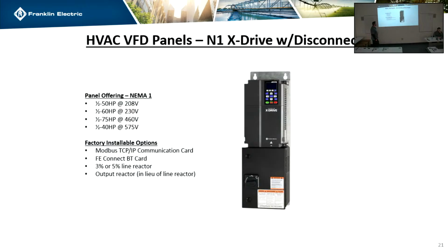Boston, you're going to have to back me up if this is still accurate. I know these are constantly changing, the panel offerings for the drive disconnects. Yep. Half horse to 50 for 208, half horse to 60 for 230. Is this still accurate? All the ratings are correct.